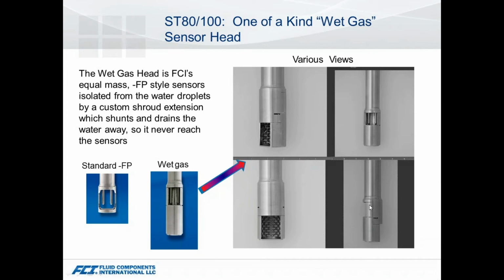One thing to keep in mind is this wet gas sensor is really more of a solution for a known instance where you've had technologies that have not been able to work properly because of the moisture that's entrained in the gas, or you want to use it as a little bit of security if you're dealing with an application like a biogas or a landfill digester gas type application, something that typically generates moisture. You don't have something in your system to knock that moisture out prior to your metering point, which would really be ideal, but a lot of times that's not feasible. So it gives you this solution.